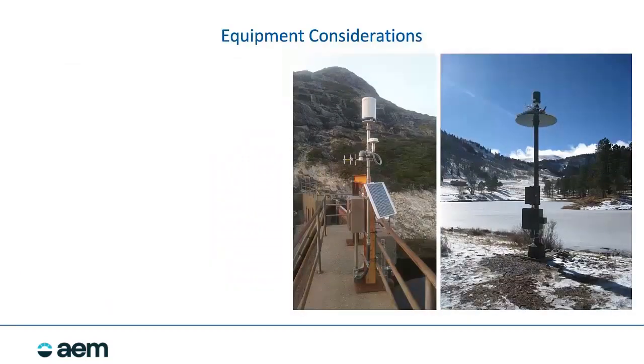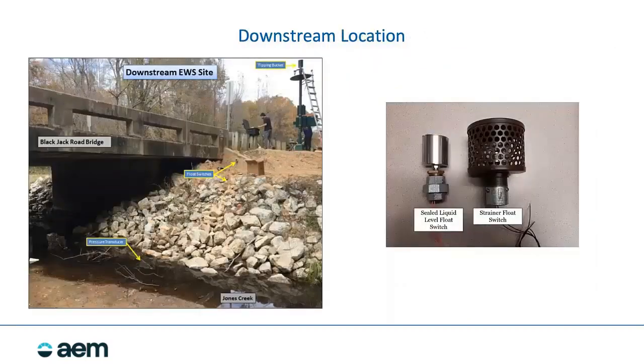The float switches here on the right, those are just two examples of a liquid level switch. Very simple, they're a cost-effective solution instead of a pressure transducer. Easily replaceable, they stand up to a lot of beating, but very basic and simplistic in design, and it gives you the ability to add critical points along the way.